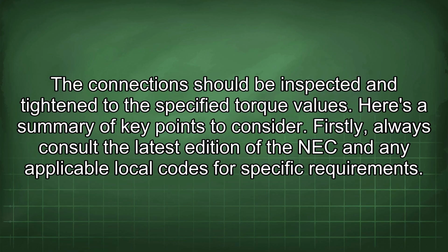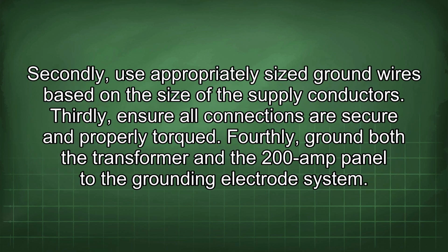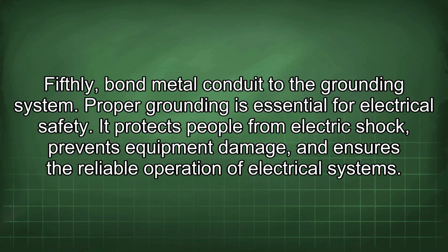Here's a summary of key points to consider. Firstly, always consult the latest edition of the NEC and any applicable local codes for specific requirements. Secondly, use appropriately sized ground wires based on the size of the supply conductors. Thirdly, ensure all connections are secure and properly torqued. Fourthly, ground both the transformer and the 200 amp panel to the grounding electrode system. Fifthly, bond metal conduit to the grounding system.